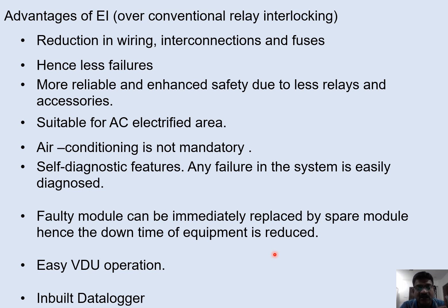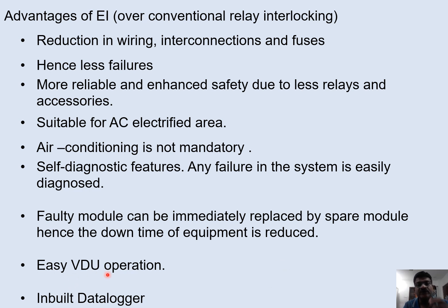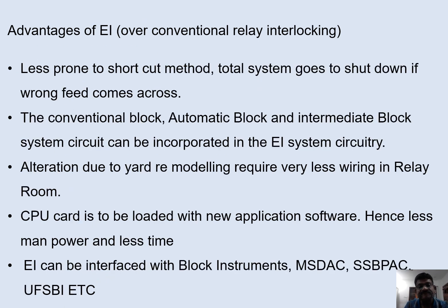All EIs are module-based and card-based. If any card is defective, it is very easy to remove: switch off the system, remove the card, replace the card, then switch the system back on. So the time for attending to faults is very short because they are module-based. VDU operation is self-explanatory and very easy. It has an inbuilt data logger. It is also less prone to shortcut methods — whenever such a thing is done, a total system shutdown occurs if a wrong feed comes across.